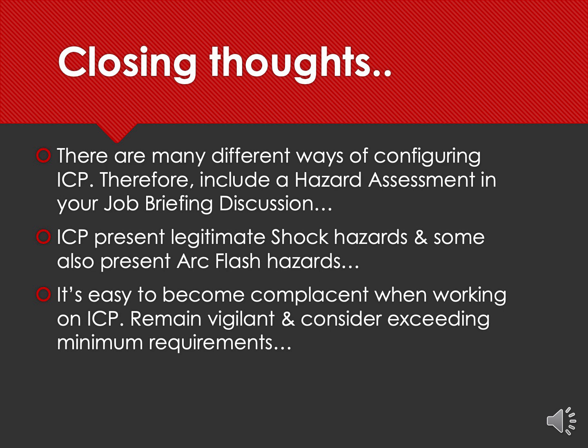The second point is that you can assume that industrial control panels present a legitimate shock hazard. This is especially true on the AC side of the equipment, but even on the DC side of the equipment when it's in the 120 volt range is also worth managing. Some, not all, may have arc flash hazards as well, especially when the source is an incoming three-phase 480 volt system that steps it down to like 120 volts. Those kinds of sources often can produce arc flash hazards that need to be assessed and managed.